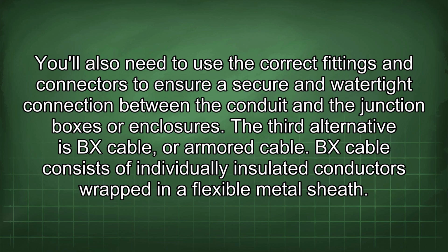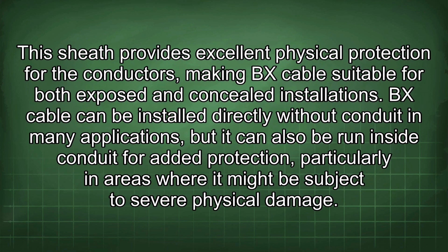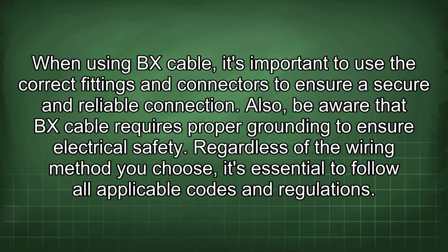The third alternative is BX cable, or armored cable. BX cable consists of individually insulated conductors wrapped in a flexible metal sheath. The sheath provides excellent physical protection for the conductors, making BX cable suitable for both exposed and concealed installations. BX cable can be installed directly without conduit in many applications, but it can also be run inside conduit for added protection, particularly in areas where it might be subject to severe physical damage. When using BX cable, it's important to use the correct fittings and connectors to ensure a secure and reliable connection. Also, be aware that BX cable requires proper grounding to ensure electrical safety.